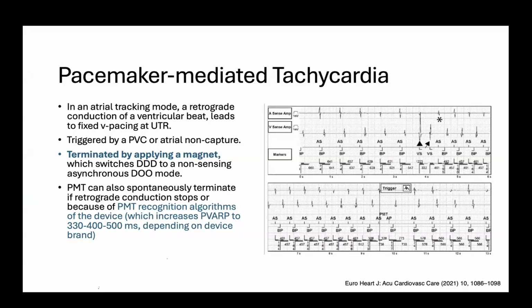Now, most of the devices have the PMT detection algorithm, where once it recognizes this issue, it increases the PVARP, or the post-ventricular atrial refractory period, to 330 in Abbott, 400 in Medtronic, and 500 milliseconds in Boston, depending, as I mentioned, on the device brand. And this could also help. But again, we've seen PMTs in patients with these devices and those algorithms activated. So it's always something to keep in mind.